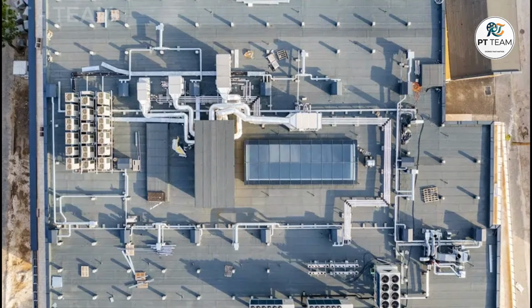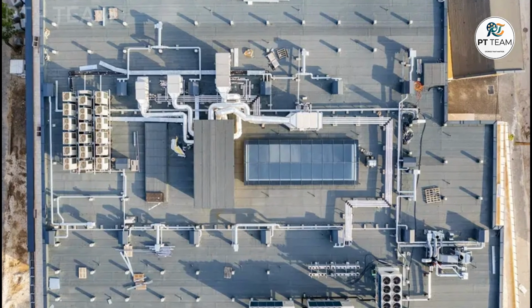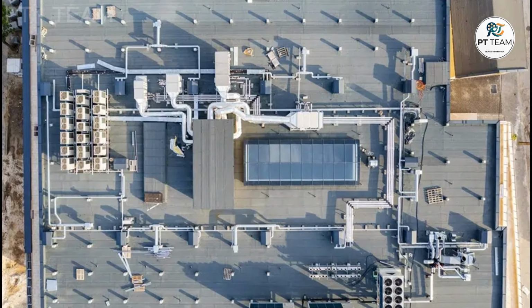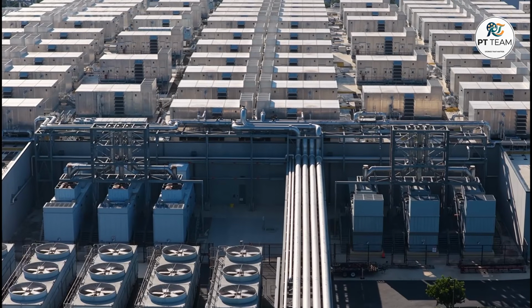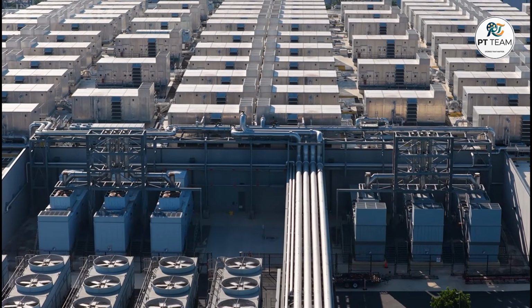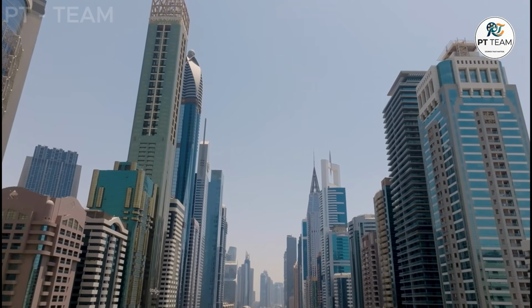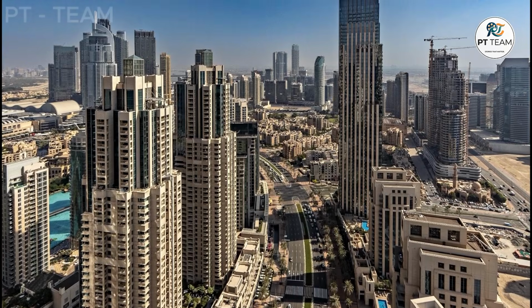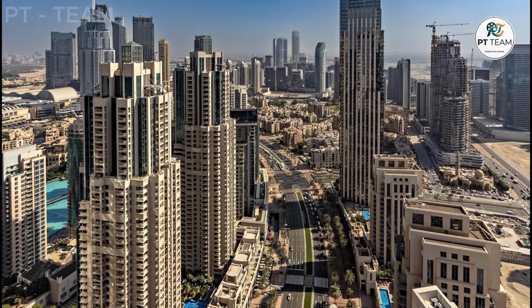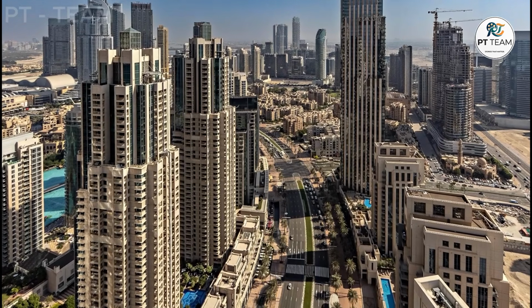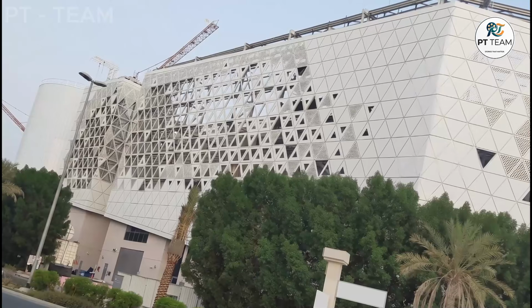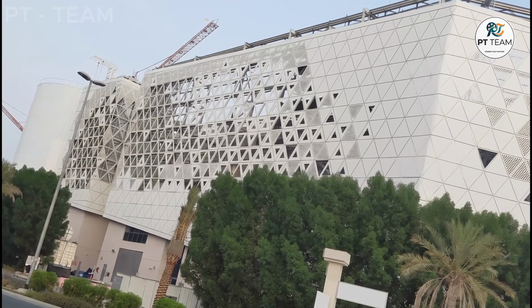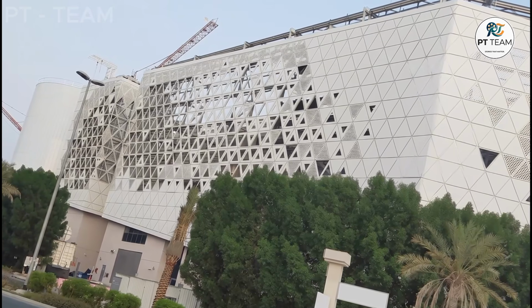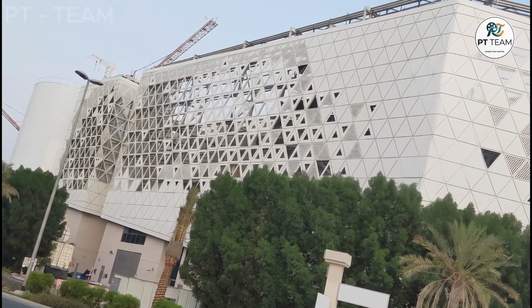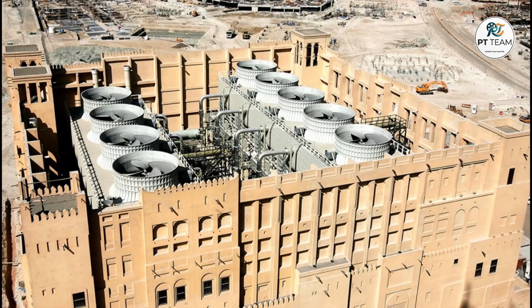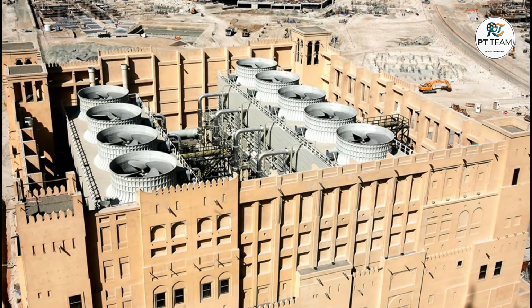A centralized system does not magically manufacture a comforting substance called cold. It systematically captures and removes heat. The more cooling these connected buildings demand, the more heat the entire infrastructure chain must capture, move, and throw away. The city is not simply asking the central plant to deliver more cold air to its lobbies and living rooms. It is actively sending the plant significantly more heat to deal with.